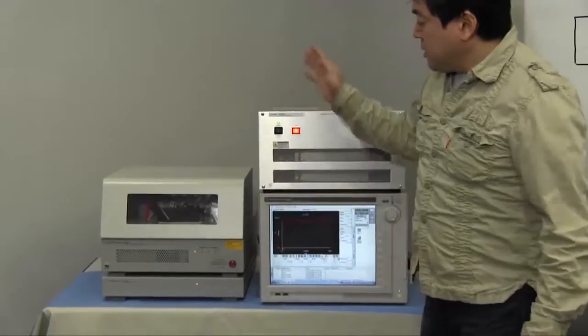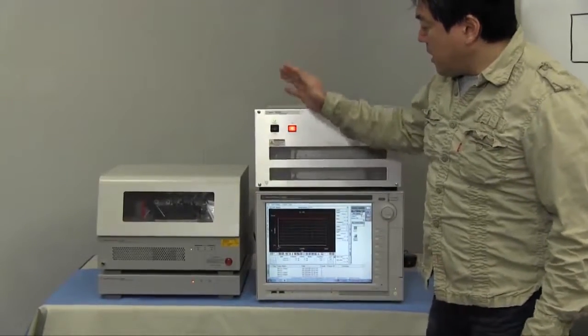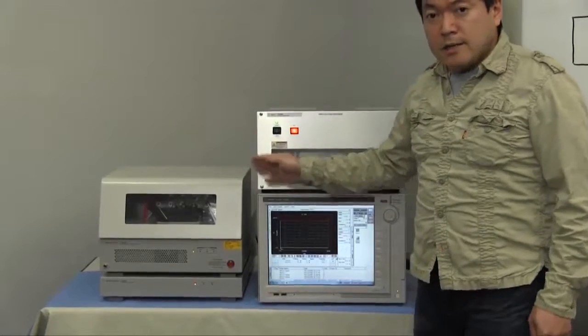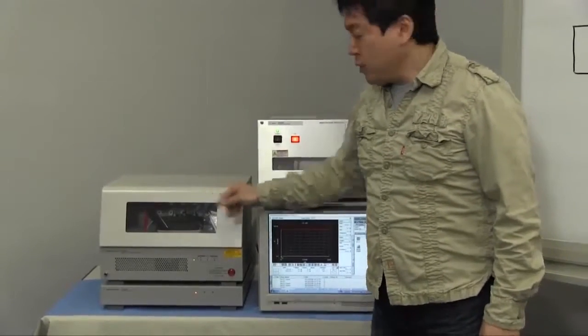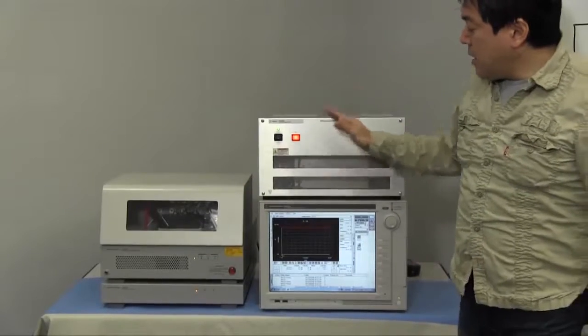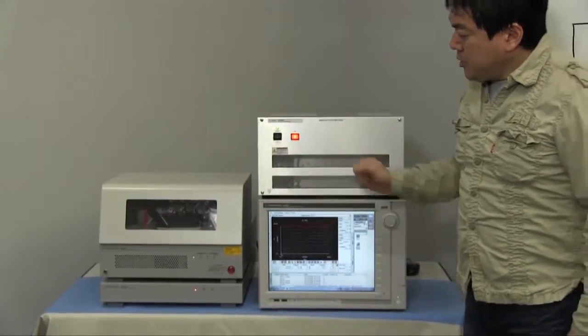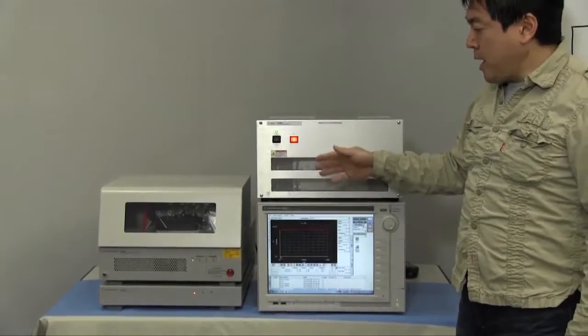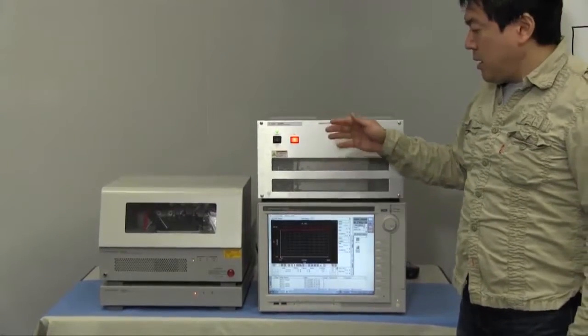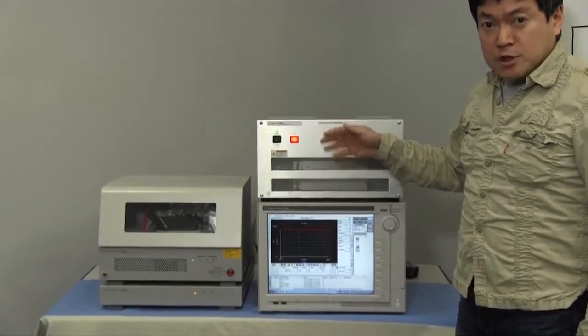Okay, so since this fixture has interlock function and also it has a shield, by using this configuration system, you can measure breakdown voltage safely without a danger of electrical shock.